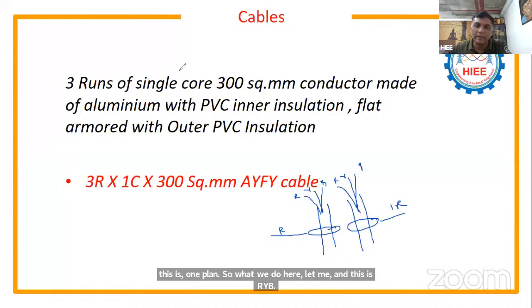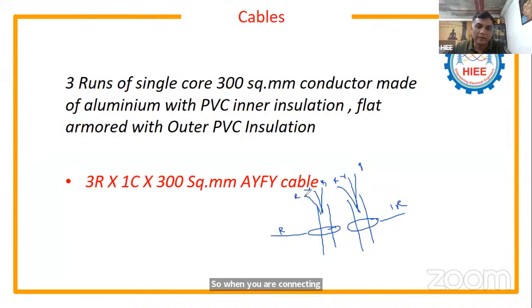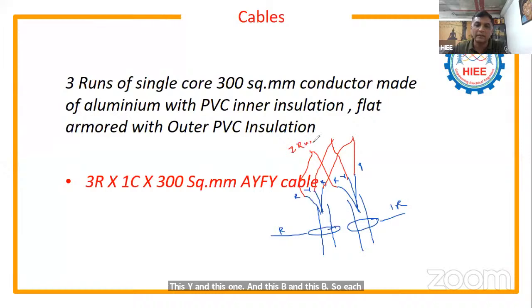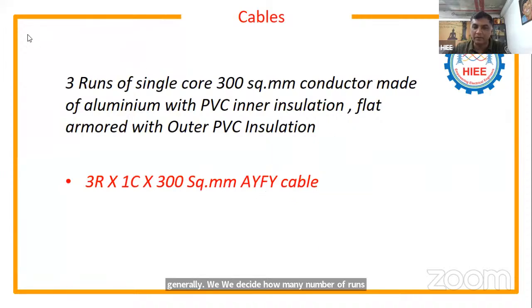So when you are connecting, this R and this R will be connected at one place, this Y and this Y, and this B and this B. So for each phase we are connecting 2 runs. This is how it will be in a practical scenario. Okay, so it depends upon the current carrying capacity. Generally, we decide how many runs shall be connected per phase.